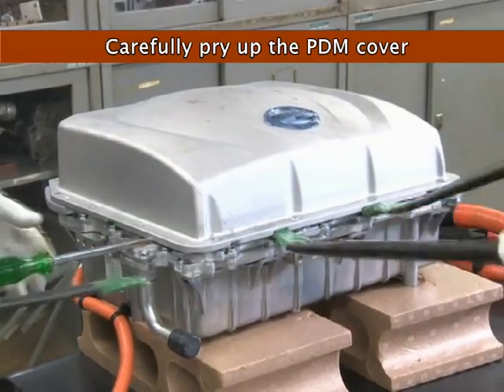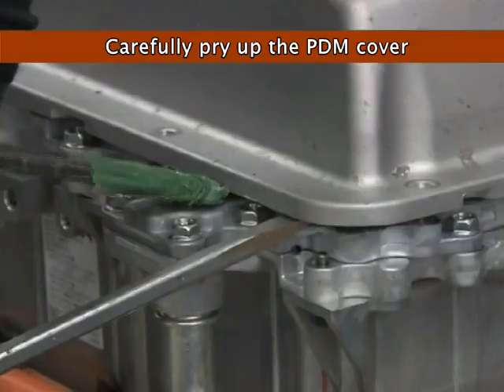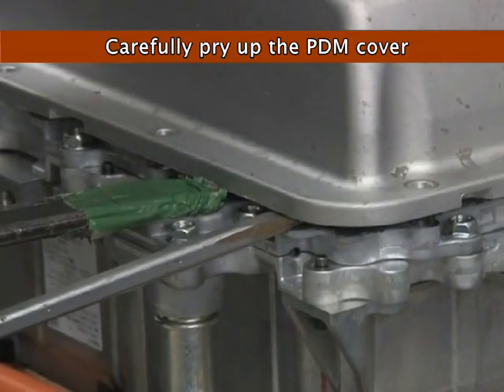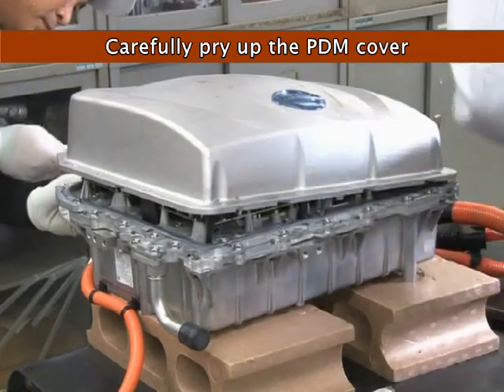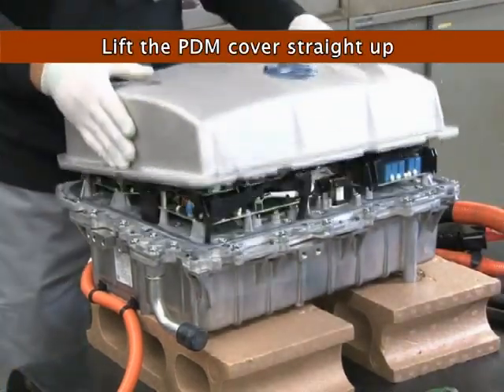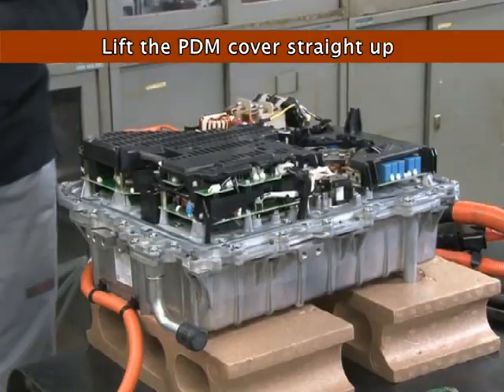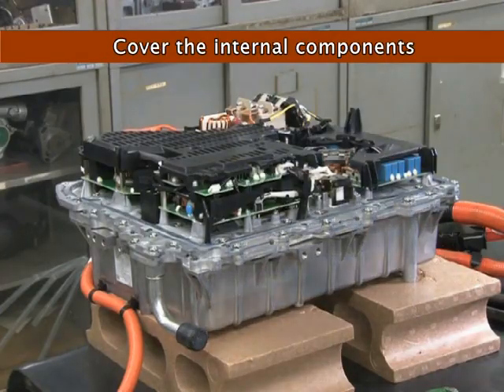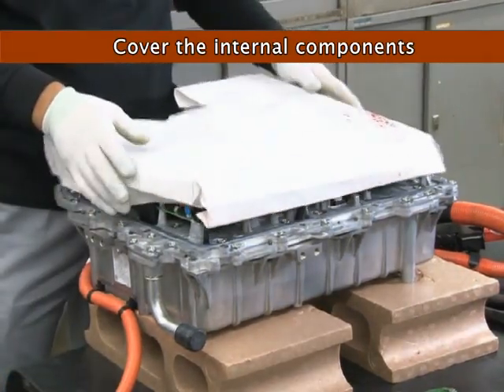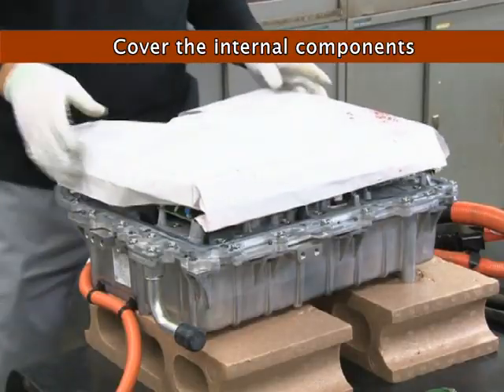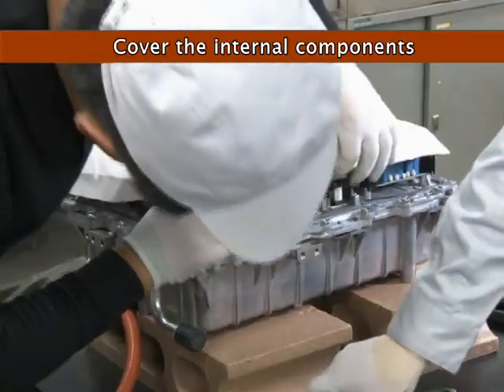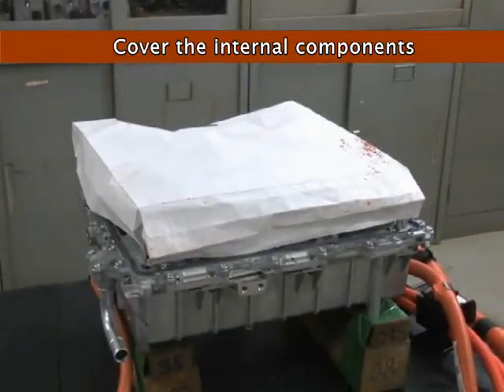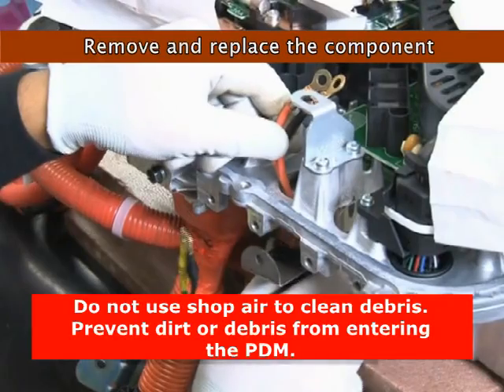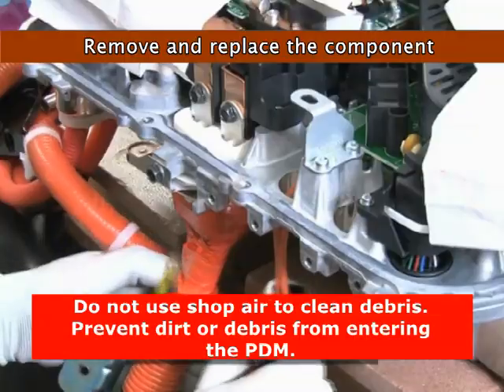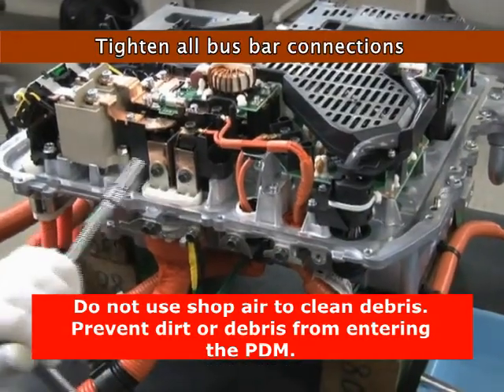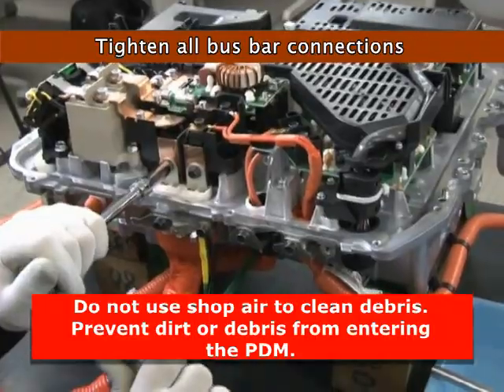Carefully pry the cover from the PDM. Use precautions such as covering the tips of the prying tools with tape to prevent damaging the cover mating surfaces. Lift the cover straight from the PDM housing. Take care not to contact any of the internal circuitry. Immediately after removing the PDM cover, install the protective cover of heavy paper or light cardboard to prevent entry of dust or dirt into the circuit board section. Remove and replace the damaged component. Carefully tighten all bus bar and harness retainer bolts to specifications.